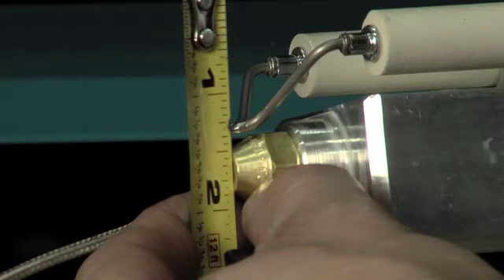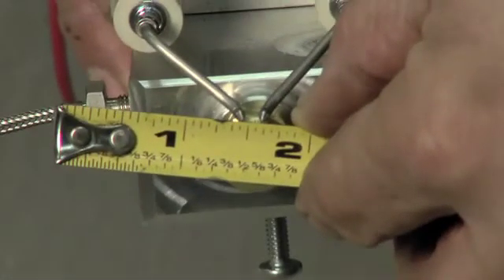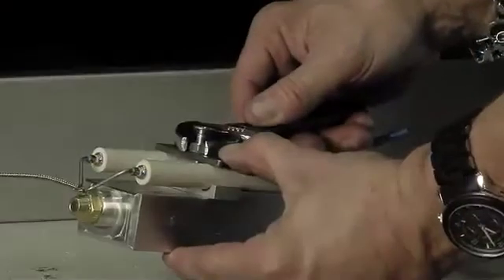The width between the tips of the electrodes is to be set at 3 sixteenths inches. Retighten the electrodes securing nut.